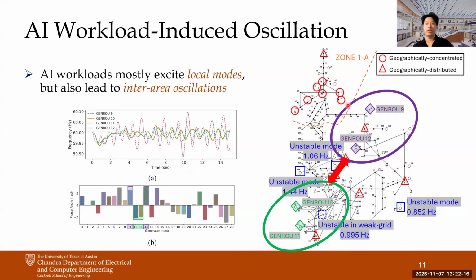So when we look at the oscillations caused by this AI workload, basically they have fluctuations around 1 Hz. They mostly excite the local modes in the grid system. But as you can see from this left figure, the generators in this purple zone and the generators in this green zone show different phases, which means that there is also inter-area oscillation. So this will be the characteristic of this AI workload driven oscillation: there's an inter-area oscillation, but the frequency of this oscillation is mostly located at the local mode frequency.